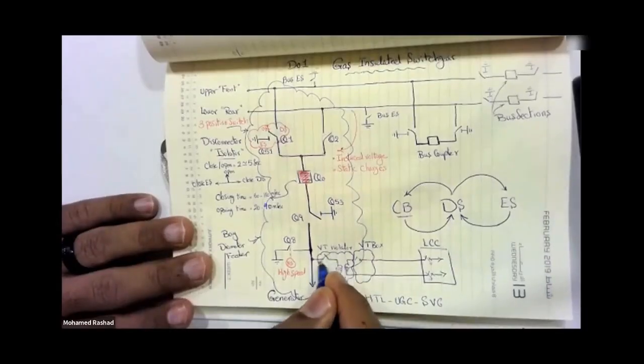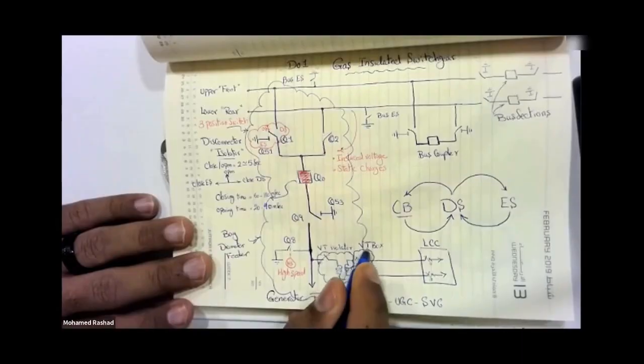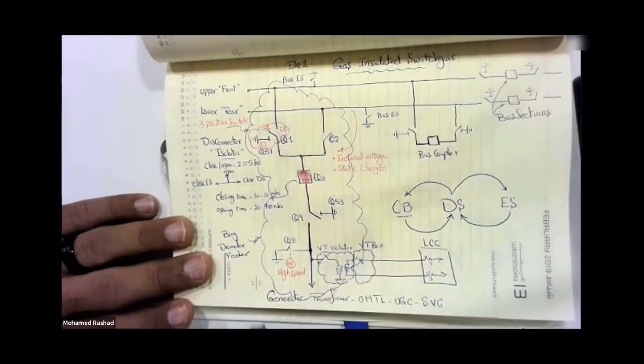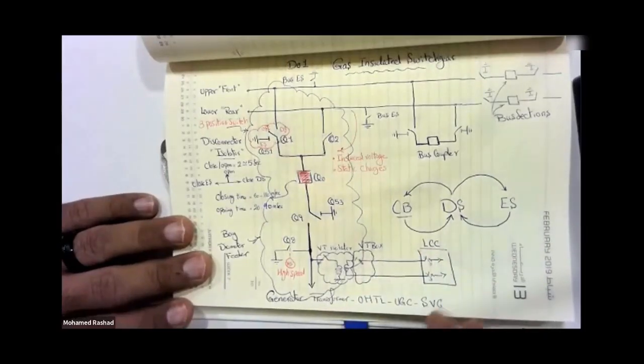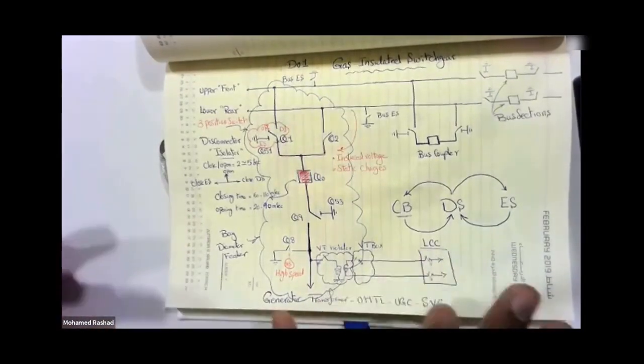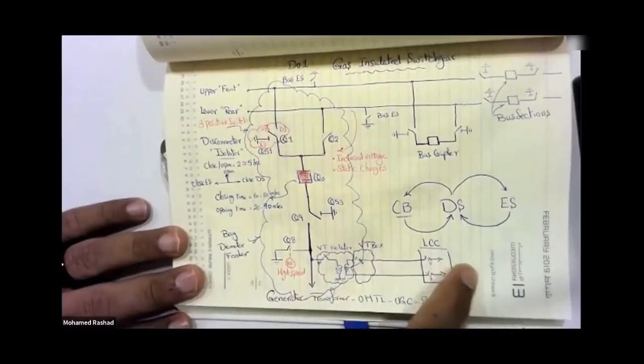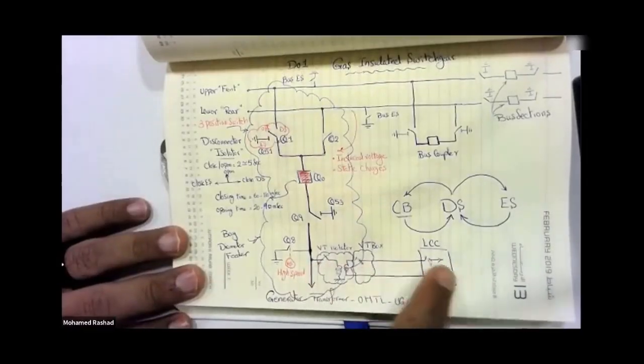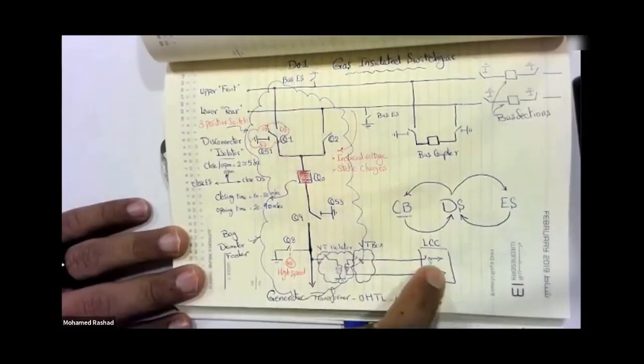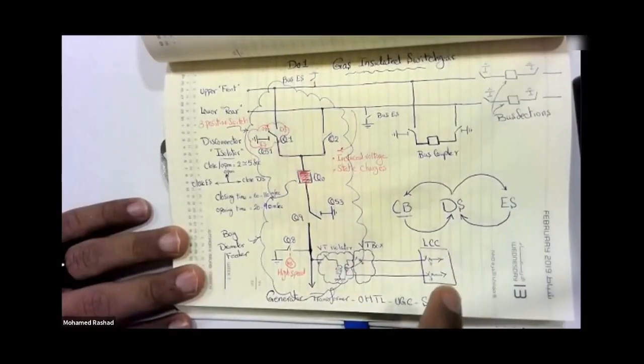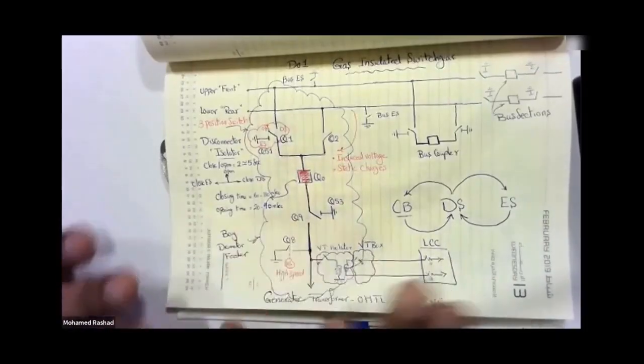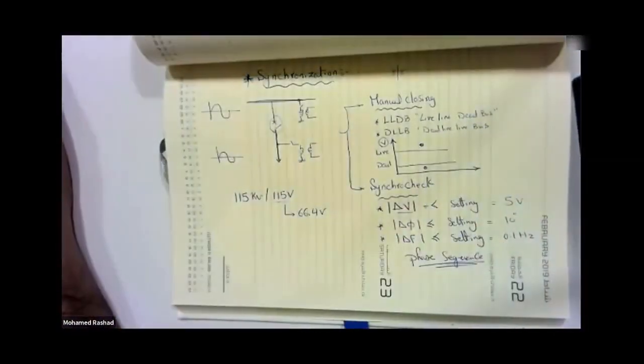So I need to make sure that the VT isolator is closed, the VT MCB in the box is closed, and the VT MCB in the LCC is closed. In this situation, if the voltage I read through the PSU, the meter relay, or the synchroscope and TFR shows 0, then indeed the voltage reaching me is actually 0, because I have confirmed that all the connections are closed. But if any one of them was open, it means that the voltage that will eventually reach the PSU or the synchroscope is not a real voltage. It's clear, right? So there's no confusion in the interlocking or synchronization.